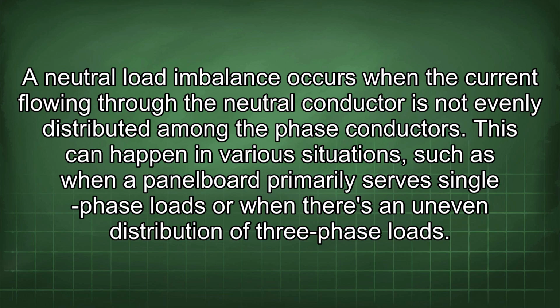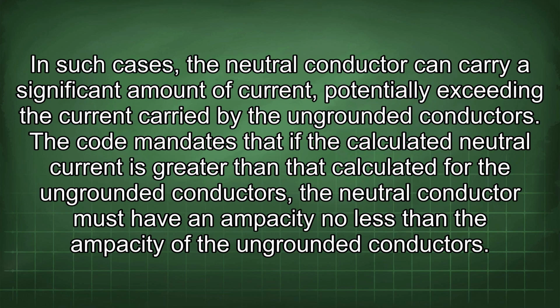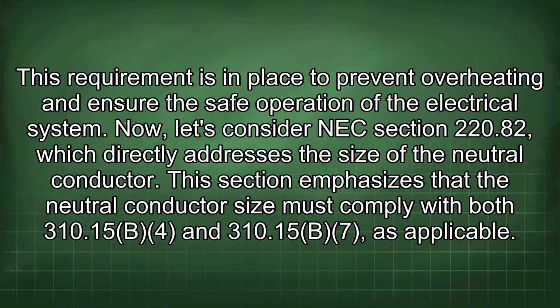A neutral load imbalance occurs when the current flowing through the neutral conductor is not evenly distributed among the phase conductors. This can happen in various situations, such as when a panel board primarily serves single-phase loads or when there's an uneven distribution of three-phase loads. In such cases, the neutral conductor can carry a significant amount of current, potentially exceeding the current carried by the ungrounded conductors. The code mandates that if the calculated neutral current is greater than that calculated for the ungrounded conductors, the neutral conductor must have an ampacity no less than the ampacity of the ungrounded conductors. This requirement is in place to prevent overheating and ensure the safe operation of the electrical system.